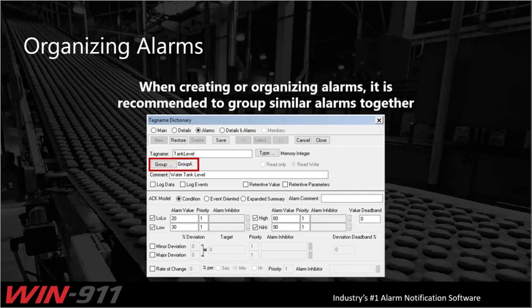For organizing alarms — when creating or reorganizing alarms in your SCADA — it's recommended to group similar alarms together, especially if you're notifying different sets of operators depending on alarm type. WIN911 subscribes to alarms based on different alarm properties such as alarm name, alarm group, and priority. InTouch allows you to assign alarms to those groups, so if you had alarms in InTouch assigned to Group A, you could easily create an alarm subscription in WIN911 for Group A and send all of those alarms to the responsible people in your call-out list.